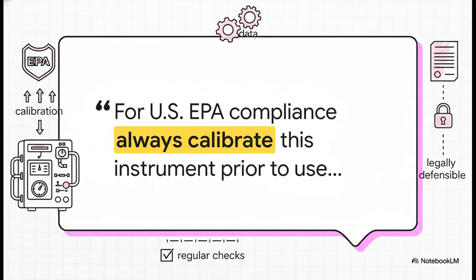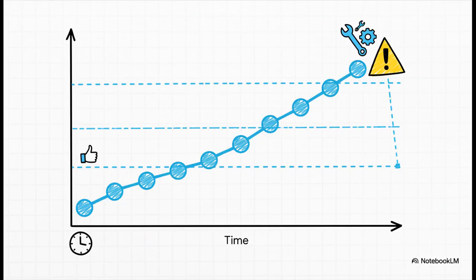The manual doesn't mess around here. It says it right there in black and white. For EPA compliance, this isn't a suggestion, it's a requirement. To keep that official EPA status we talked about, these checks are mandatory. And this is where it gets really powerful. By doing these checks regularly, and this is key, logging those slope and offset values every time, you can start to see trends. Maybe you notice the slope is slowly drifting down over a few months. That could be a sign that a part is wearing out, letting you fix it before it fails and ruins your data. It's predictive maintenance.